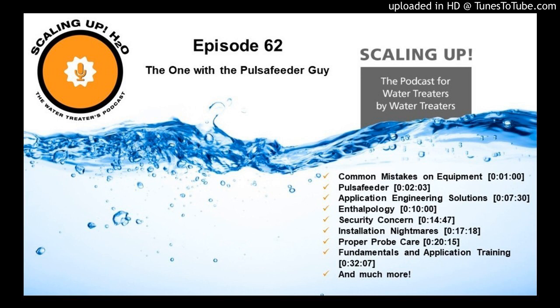So thinking out loud, what you're saying is in your flow assembly, you want those probes to be at the bottom of the assembly so they don't run out of water. Yeah, if you can put a mini trap where it's just a step. Okay, so the level drops down, and you want the probes going into that lower section of pipe, the one that should ideally not drain because you have a little trap there. All right, that's great advice.